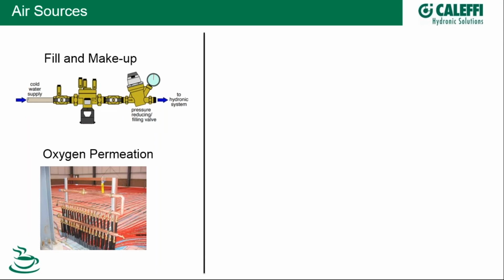Certain systems like radiant systems or any system that has non-oxygen barrier tubing, it doesn't necessarily have to be just PEX, but it could be polyethylene used in geothermal systems. You have different types of polymer piping now, very common in the marketplace, not oxygen barrier, by the way.